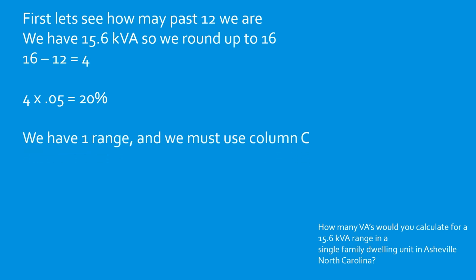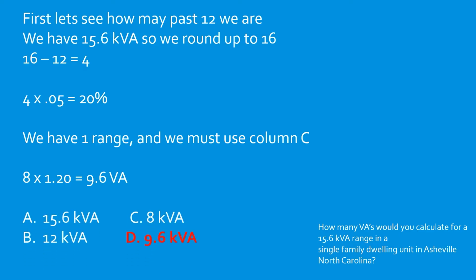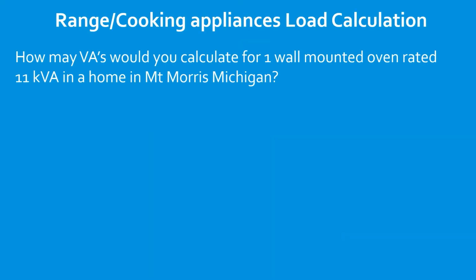Now we go back to our original table and we go through the motions. We start on the left-hand side and find our number of ranges. Then we come over to our respective column, which in this case is column C, and we figure out what our base value is. Our base value is 8 kVA. So we take 8 multiplied by 1.20, that's going to give us 9.6 kVA, and we're going to select D. Great job.